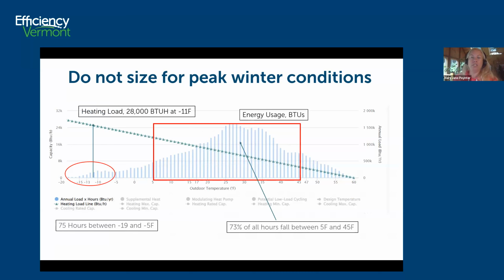So here's a pitch on not sizing for peak winter conditions. 73% of all hours fall between 5 degrees and 45 degrees outdoor air temperature. So if you're sizing up or buying multiple heat pumps to cover 5 degrees and below, it doesn't represent a very large percentage of the hours of the year. And if you already have a backup heating system that can handle 5 degrees and lower, and that allows you to buy fewer heat pumps or smaller heat pumps, it makes the whole cost effectiveness calculation a win.